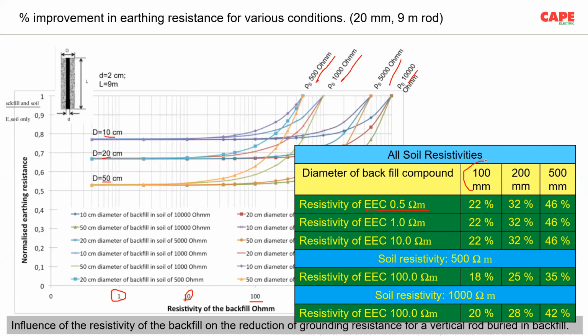If you have 100 millimeters, about 4 inches, of area filled with this particular material, then the improvement of the final RE you are getting is about 22%. What does it mean? In a typical soil without earth enhancing compound, imagine the resistance you are getting is 10 ohm. With earth enhancing compound of 100 mm all around the electrode, you get 22% improvement. That means the value is something about 7.8 ohm instead of 10 ohm. But remember, you should put 100 millimeter all around the electrode.